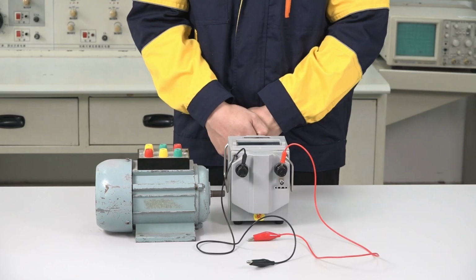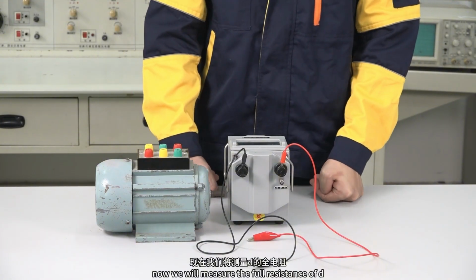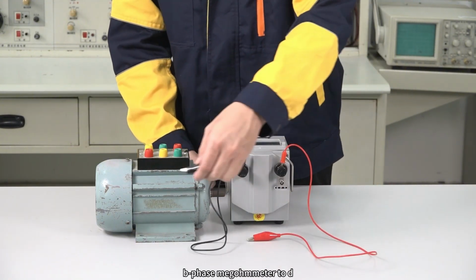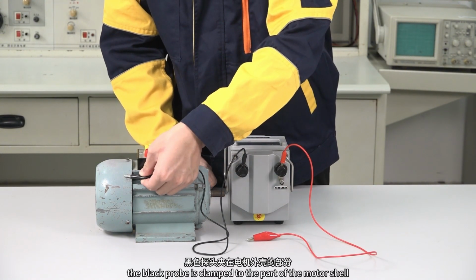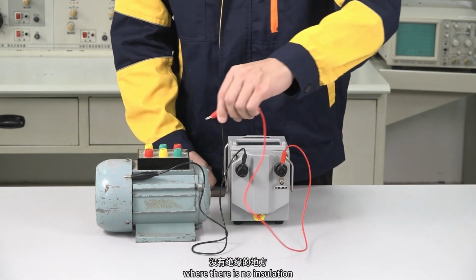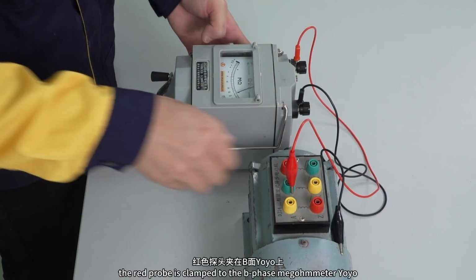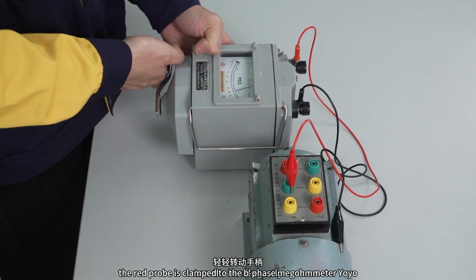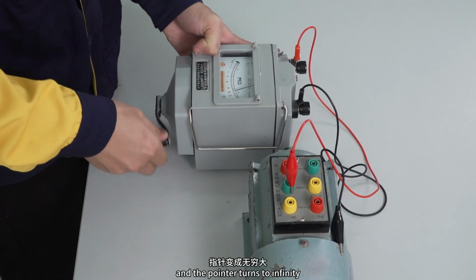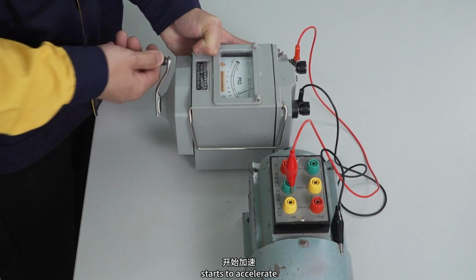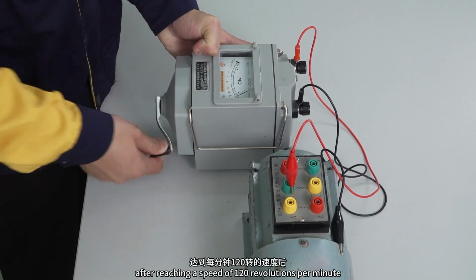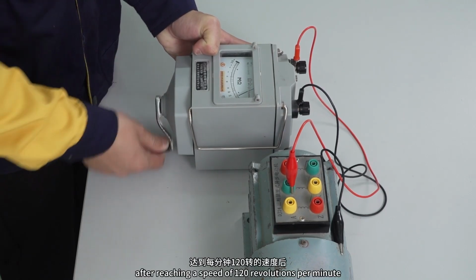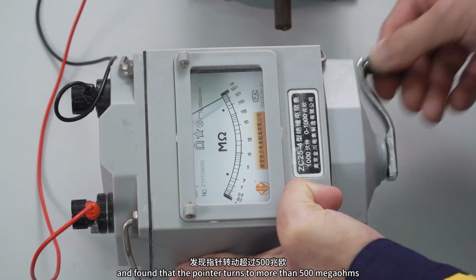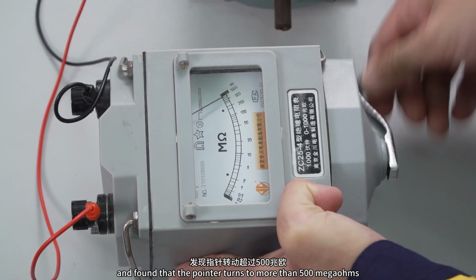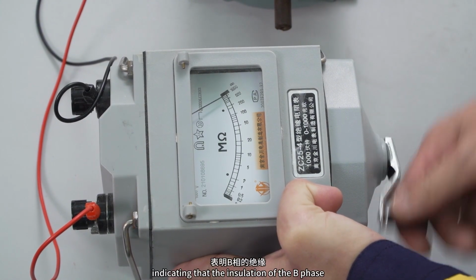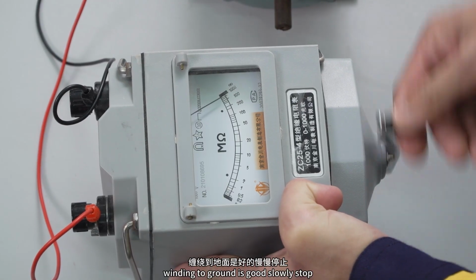Slowly stop. Now we will measure the insulation resistance of B phase to ground. When measuring, the black probe is clamped to the part of the motor shell where there is no insulation. The red probe is clamped to the B phase. Turn the handle gently and the pointer turns to infinity. Start to accelerate. After reaching a speed of 120 revolutions per minute, the pointer turns to more than 500 megohms, indicating that the insulation of the B phase winding to ground is good. Slowly stop.